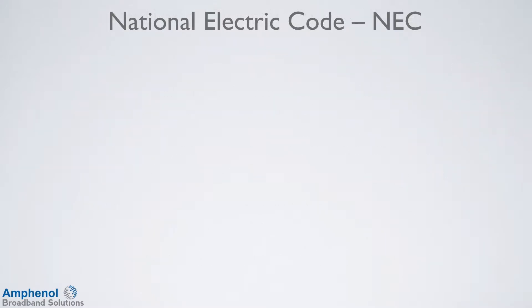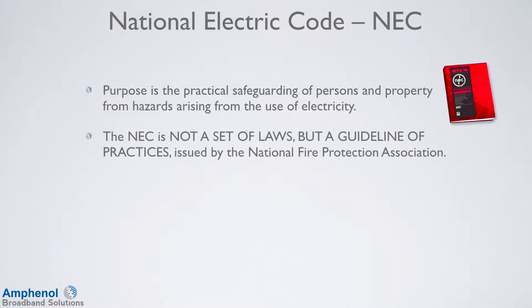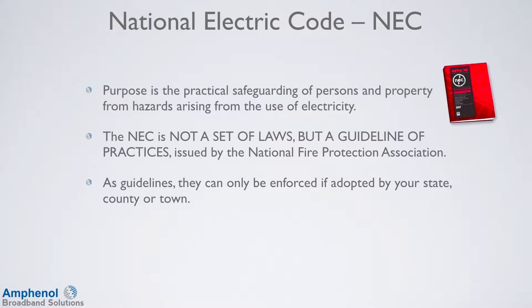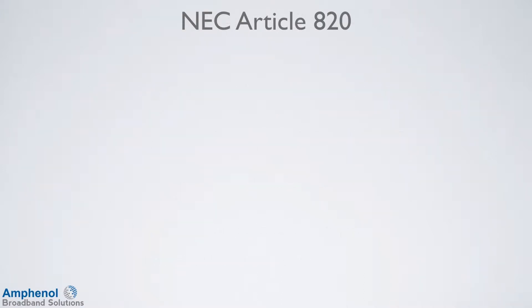The purpose of the NEC is the practical safeguarding of persons and properties from hazards arising from the use of electricity. As with the NESC, the NEC is not a set of laws but a guideline of practices issued by the National Fire Protection Association. They can only be enforced if adopted by your state, county, or town. Check with your local electrical inspector to see if they adopted the NEC and if they have more stringent guidelines. The NEC is updated every three years, and some municipalities may still be enforcing earlier versions. Article 820 of the NEC sets the guidelines for cable TV.